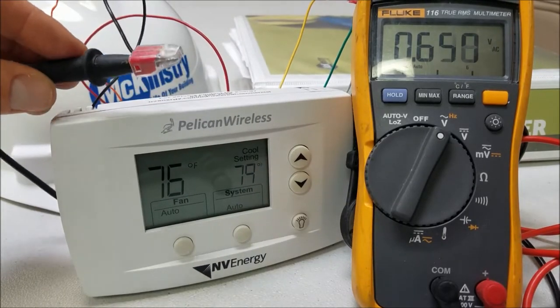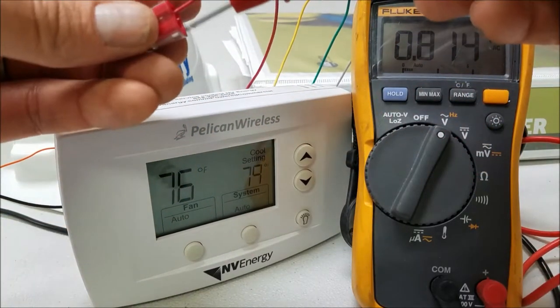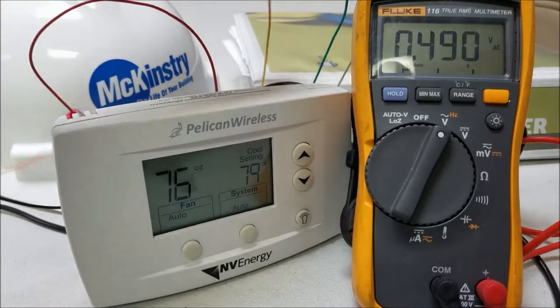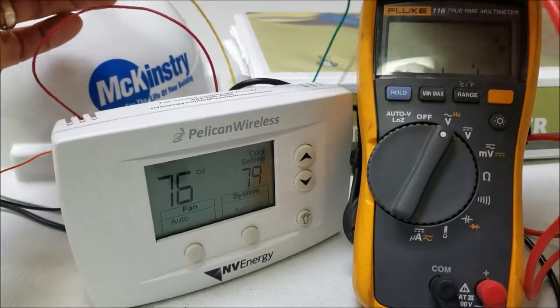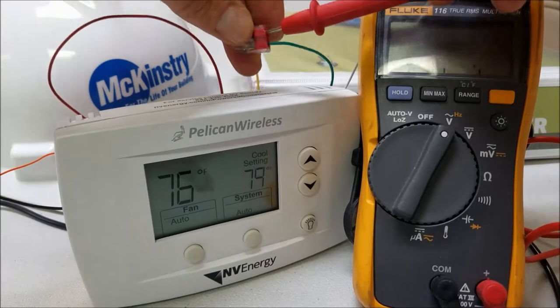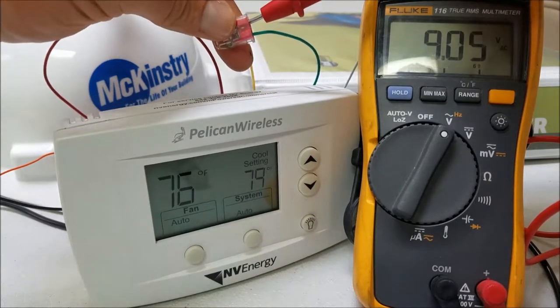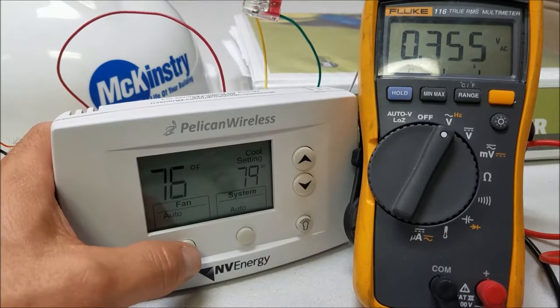I just have the common from my voltmeter plugged into the black wire. Showing you real quick: the red wire is 24 volts, the compressor's yellow wire is nine volts, and the supply fan's green wire is nine volts.